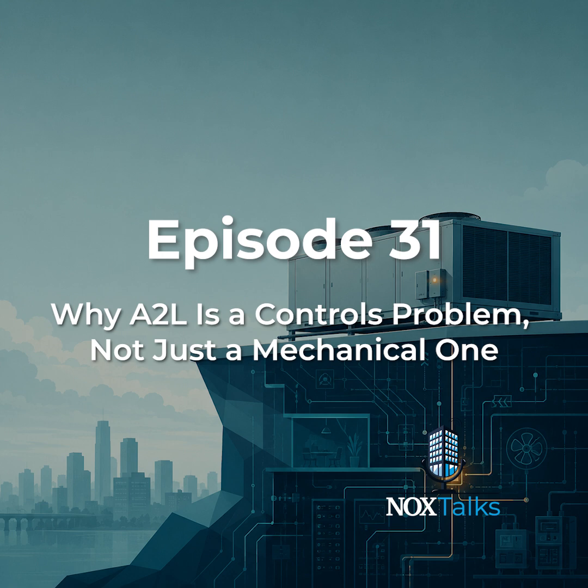Here's the part worth your attention. Some A2L equipment ships with refrigerant detection, leak sensors, plus a mitigation sequence. And those sensors don't just beep, they can trigger fans to disperse refrigerant, open dampers, shut down compressors, even de-energize duct heaters, all within defined response times. Now here's the nuance I want you to hear. Sometimes that whole sequence lives inside the unit's own factory controls. You don't touch it. But other times, the detection system has to trigger external fans, open remote dampers, raise alarms, or get monitored centrally. And the moment that's true, it becomes a controls and BAS coordination item, not just a mechanical one. New points, new sequences, new commissioning.